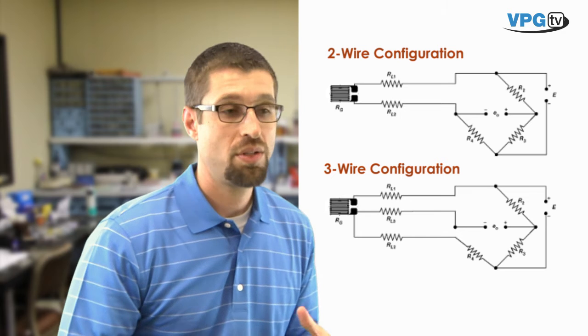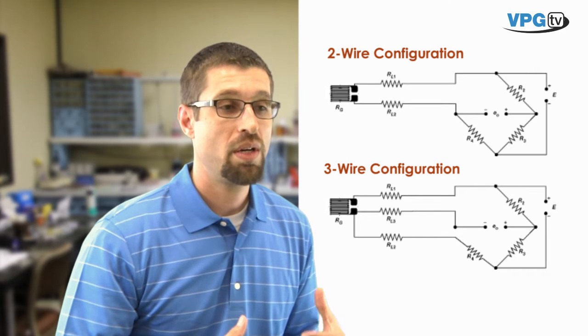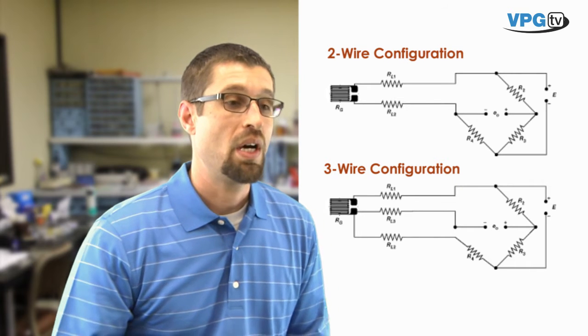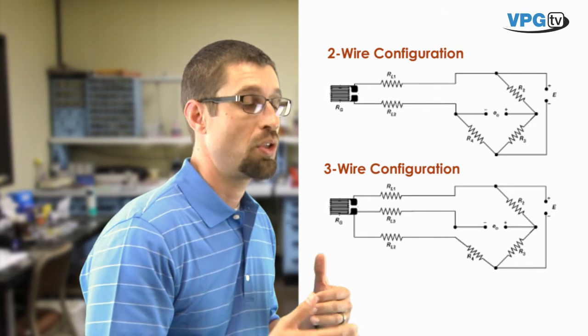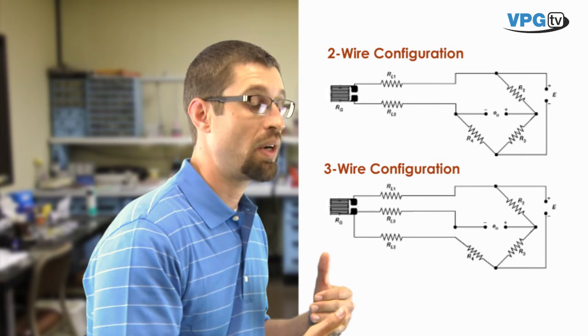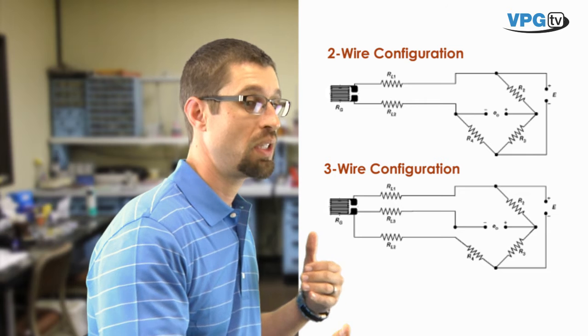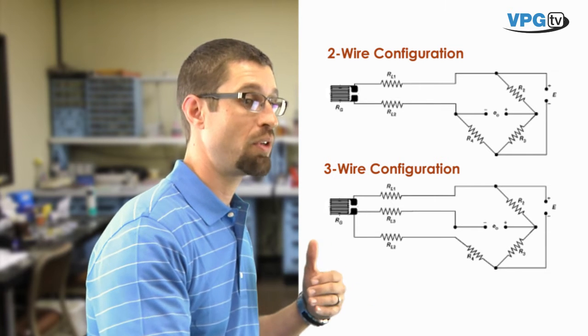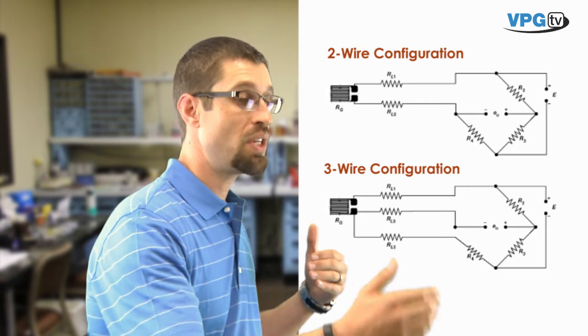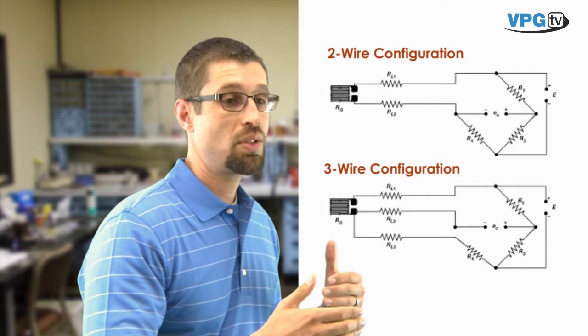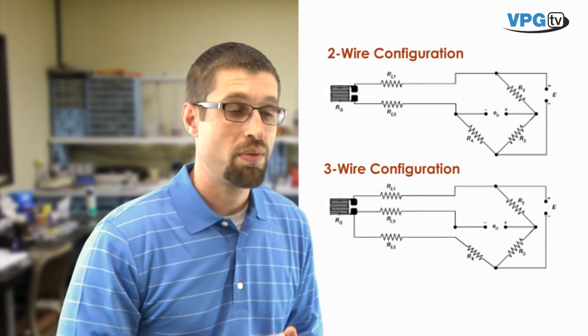The second issue is going to be error introduced into your reading from temperature fluctuation during your testing. As the temperature changes, you have resistance changes within the lead wire and of course the longer the lead wire is, the more resistance you have and the more temperature change you have during your testing, the more resistance change you have and that resistance change in a two-wire setup actually introduces error into your readings.